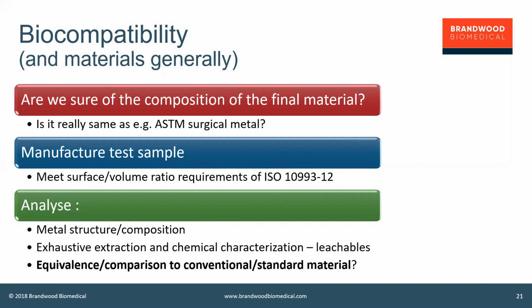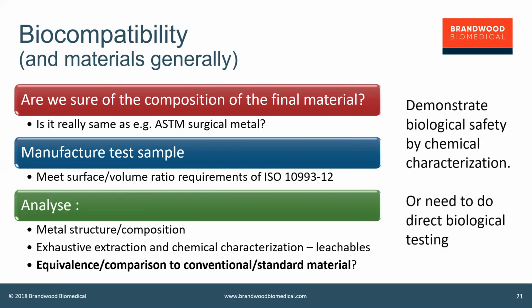You could take this one step further and say, well, here is an equivalent device manufactured not from additive manufacturing processes, but from conventional processes, which has got an established track record, and you can do a comparative analysis of that and show that what you get coming out of your device is similar to or less than what comes out of a conventionally manufactured device. So there's that way to look at it as well. So the idea is to demonstrate biological safety by chemical characterization.